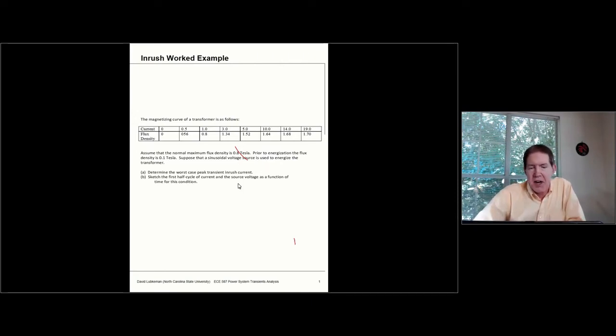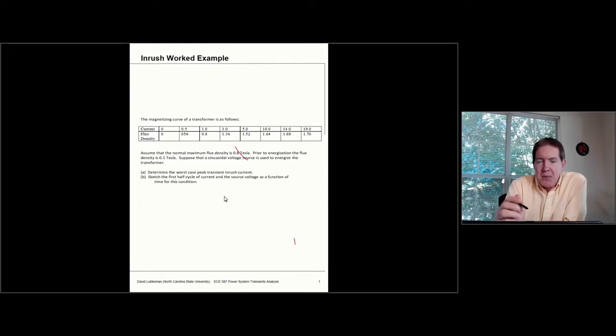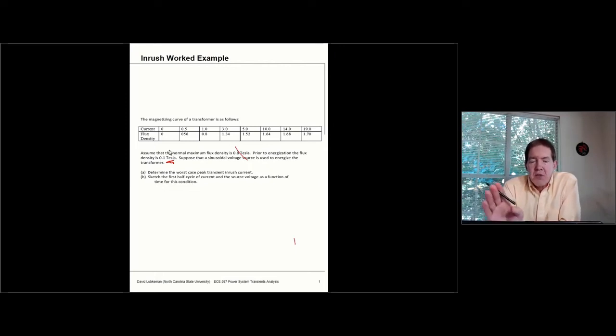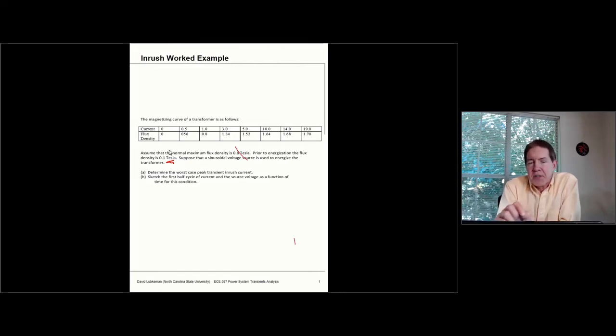Prior to energizing this transformer, we're going to have a residual flux density of 0.1 Tesla. Based on how the transformer has operated before, we'll have this residual value to work with as well. So if I'm energizing this transformer, I'm going to figure out what's the worst-case peak inrush current, and we'll sketch what's going to happen during the first half cycle to see how this current changes.